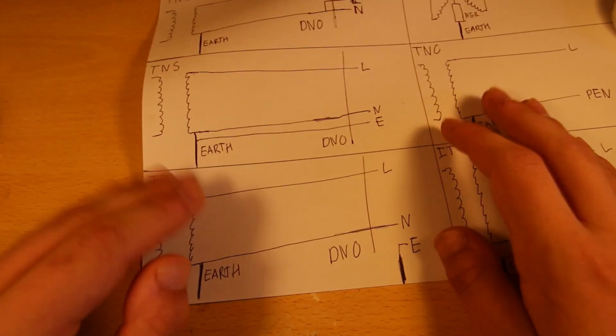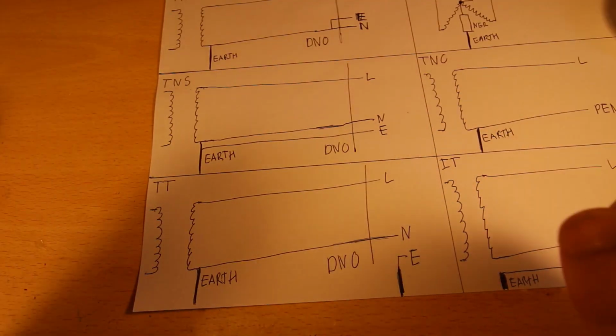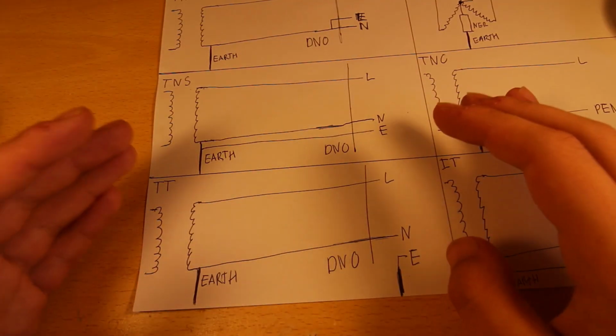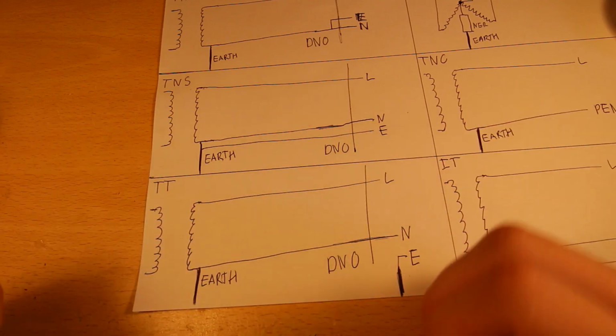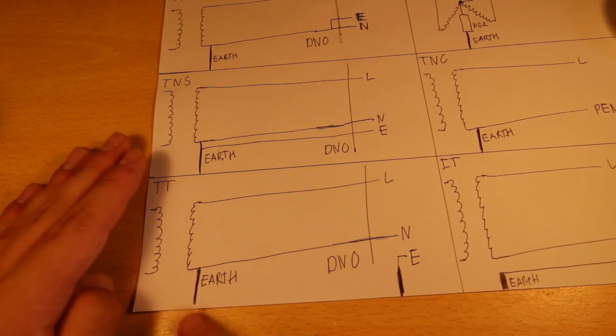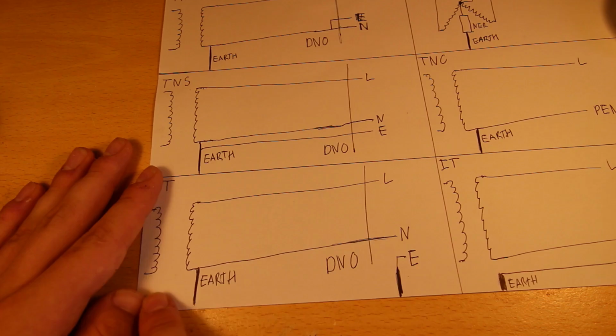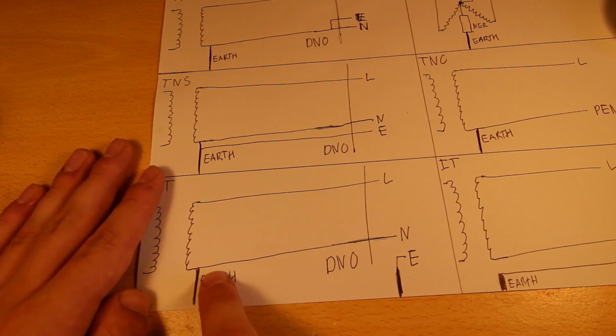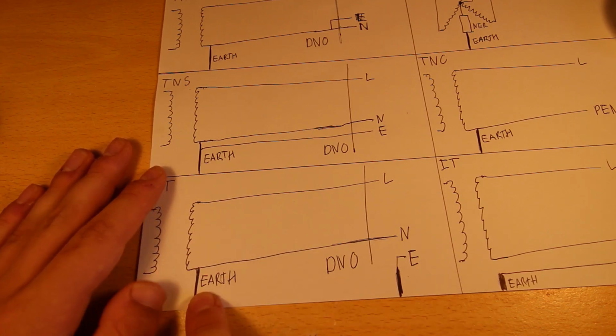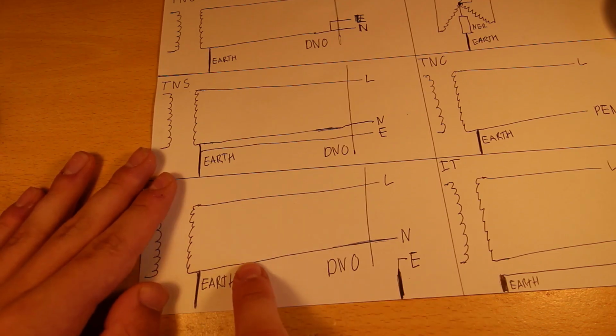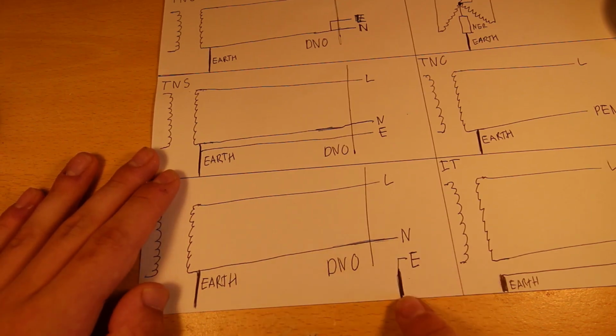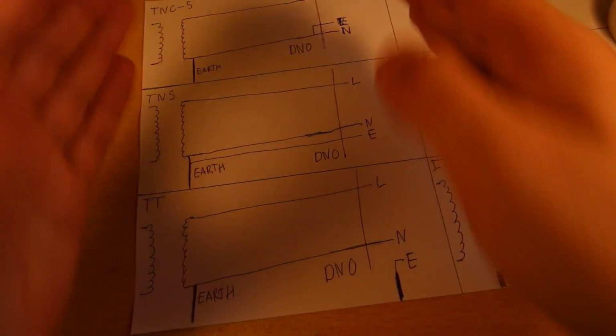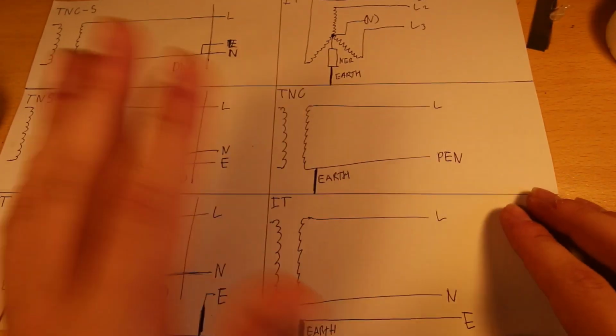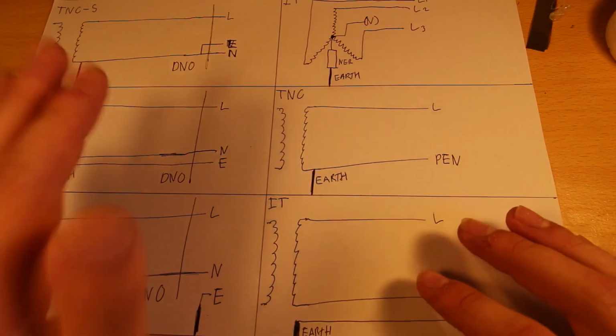And then finally we have what I would say is the best compromise now due to RCDs, which is TT, standing for earth to earth, terra terra. So the supplier have their transformer, 11 kV comes in, secondary winding here, they earth the neutral at the transformer, they then give you a live and a neutral, nothing else. You have your own earth electrode which provides the local earth for your installation. These are the 3 most common ones. These other ones you will probably never come across unless you're doing something very, very weird.